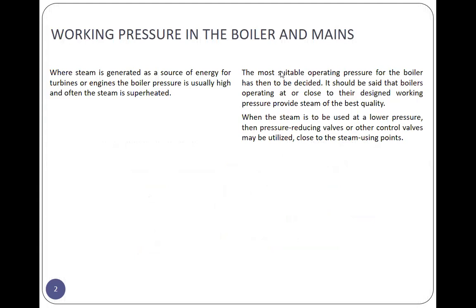So, what is the working pressure and the boiler and the mains? In the main, ito yung pipe na pinakamalaki. Where steam is generated as a source of energy for turbines or engines, the boiler pressure is usually high and often the steam is superheated. And the most suitable operating pressure for the boiler has then to be decided. It should be said that boilers operating at or close to their designed working pressure provide steam of best quality.